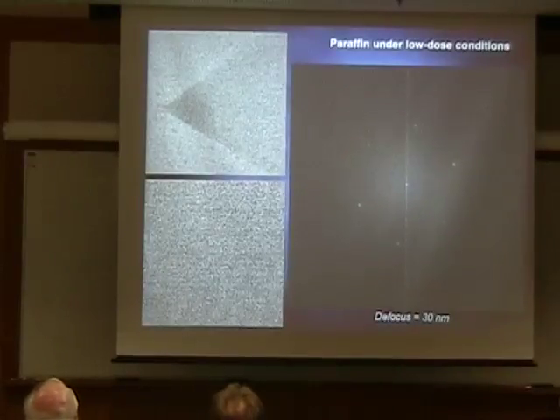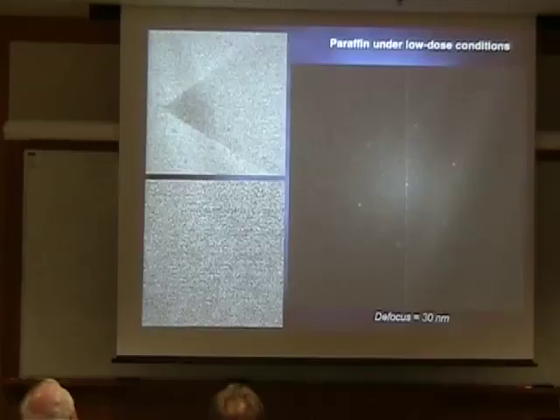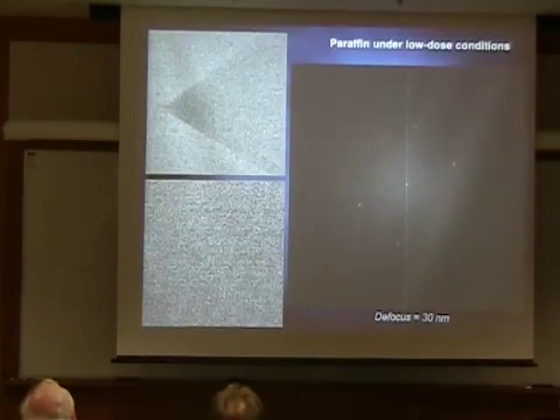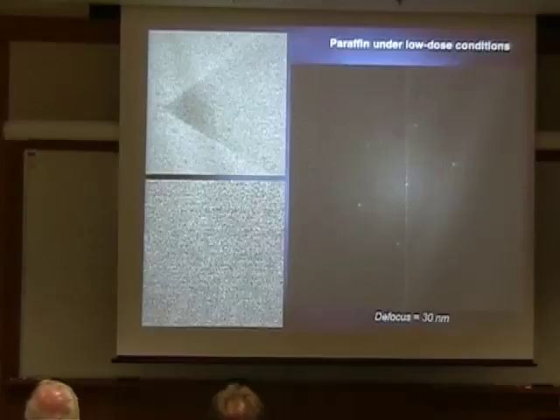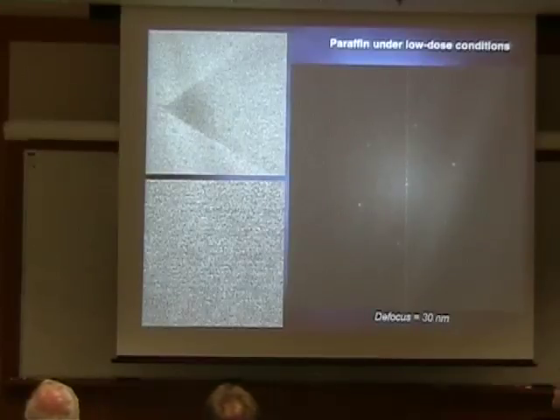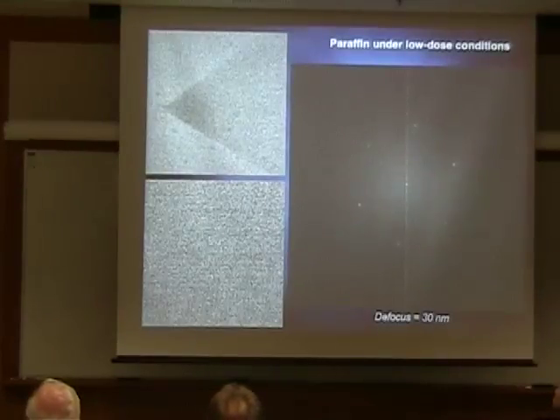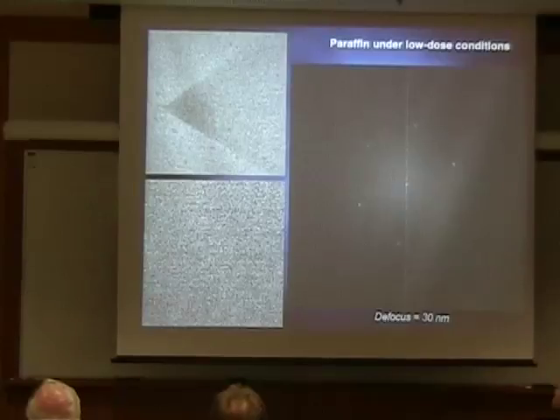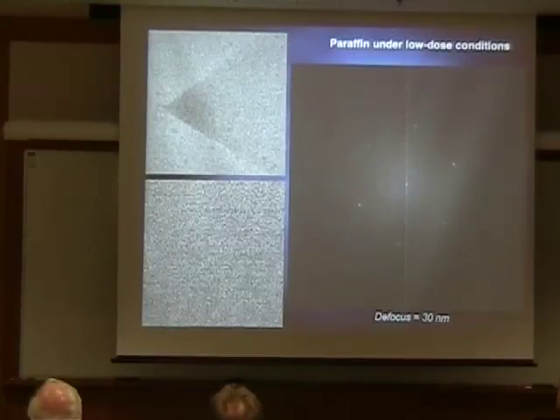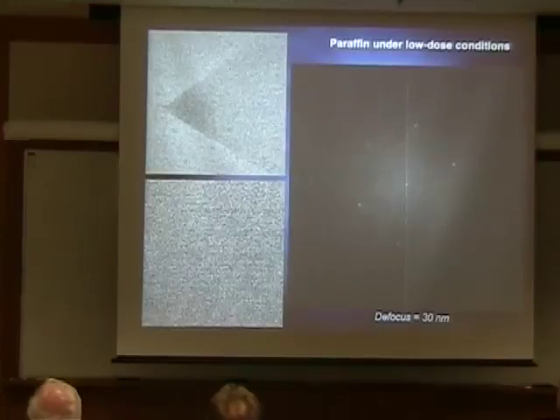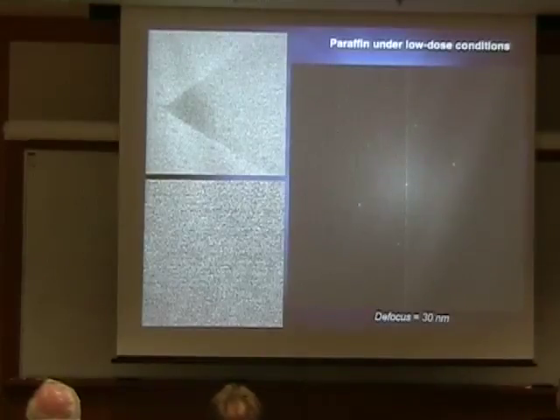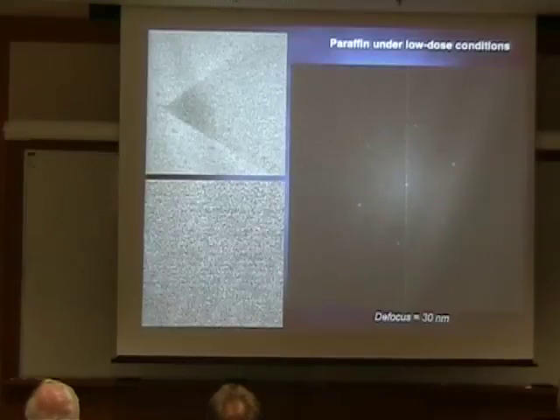The identical microscope at Argonne National Labs — I went to test the STEM to see it — they only have the STEM CS corrector. But they replaced their two oil diffusion pumps with two turbo pumps, and there was absolutely no contamination. We were doing the exact same experiments with no problem.